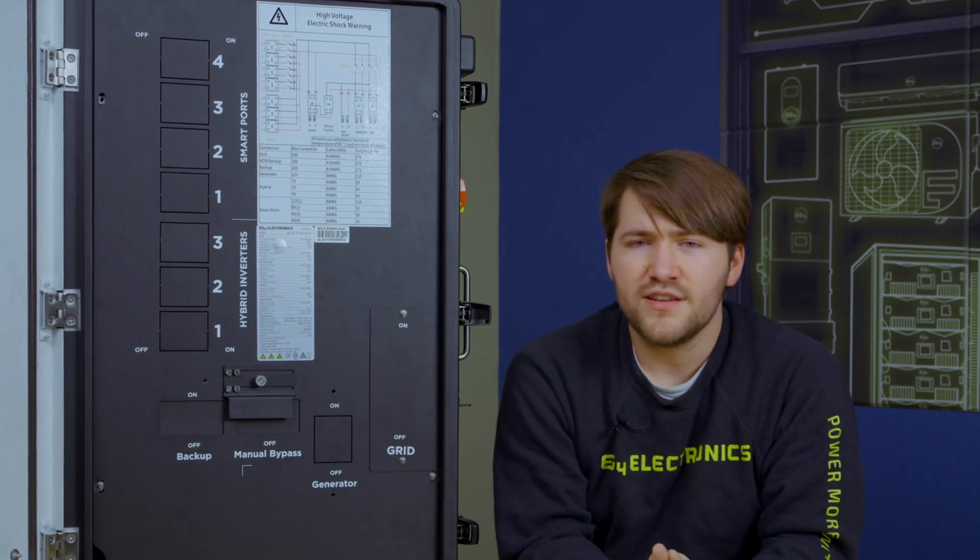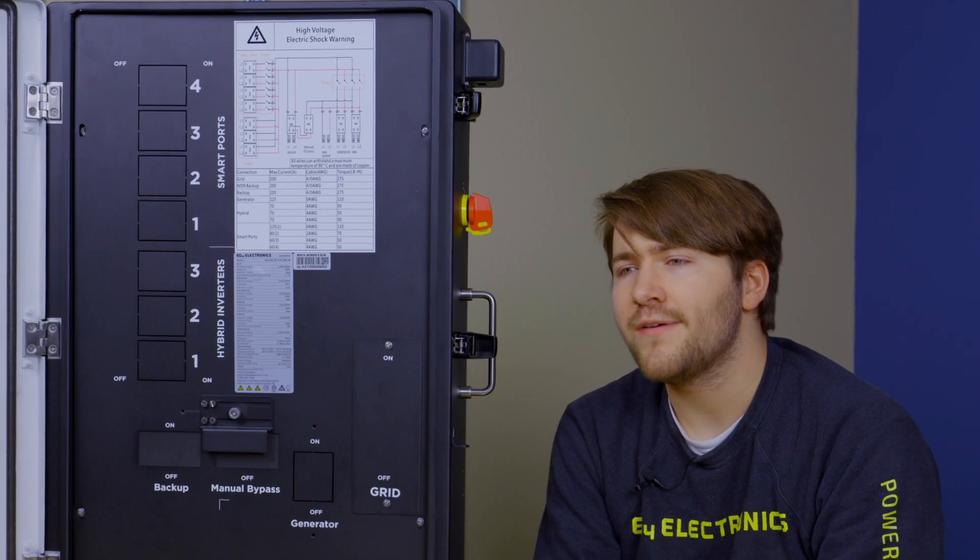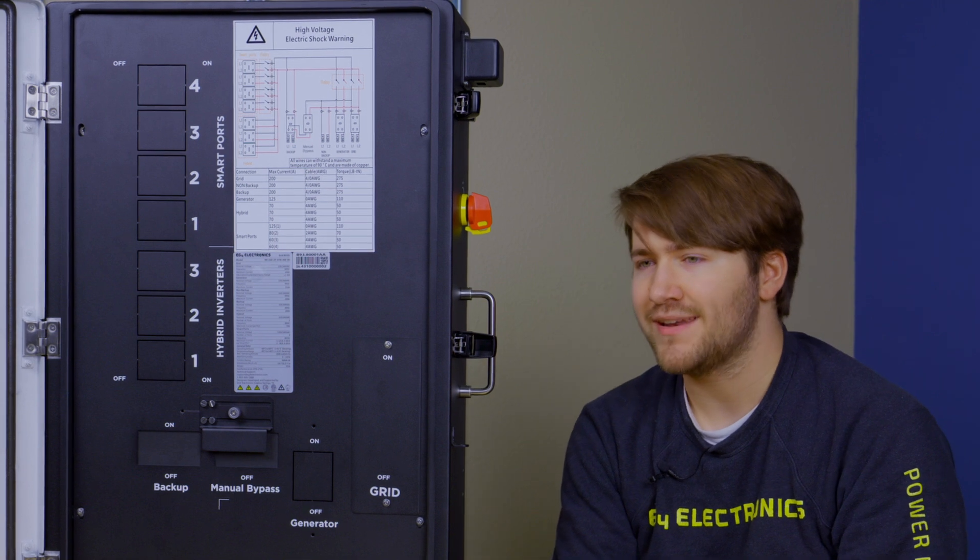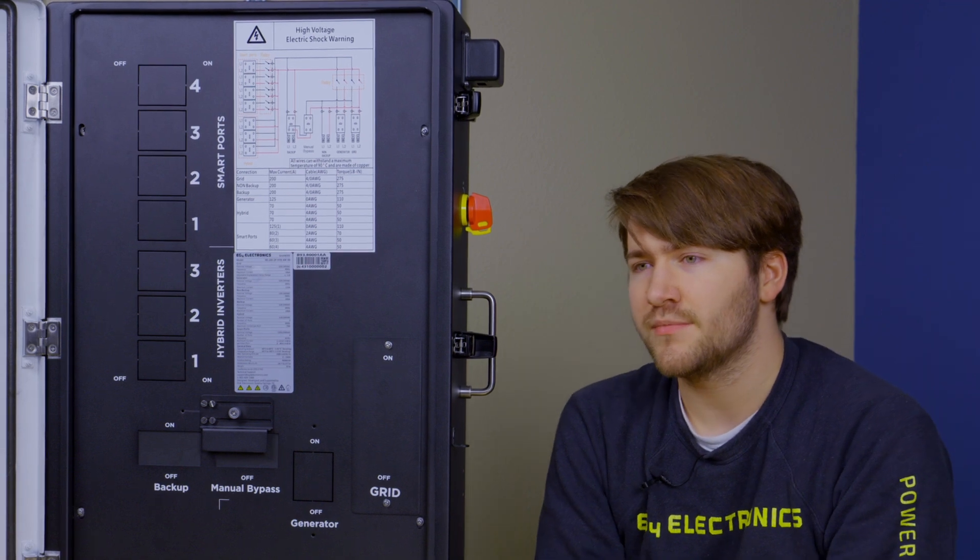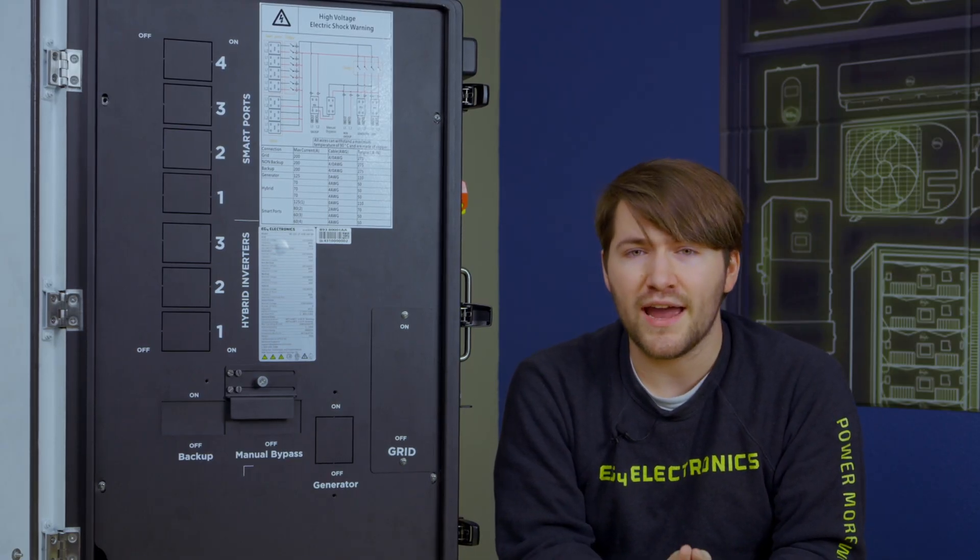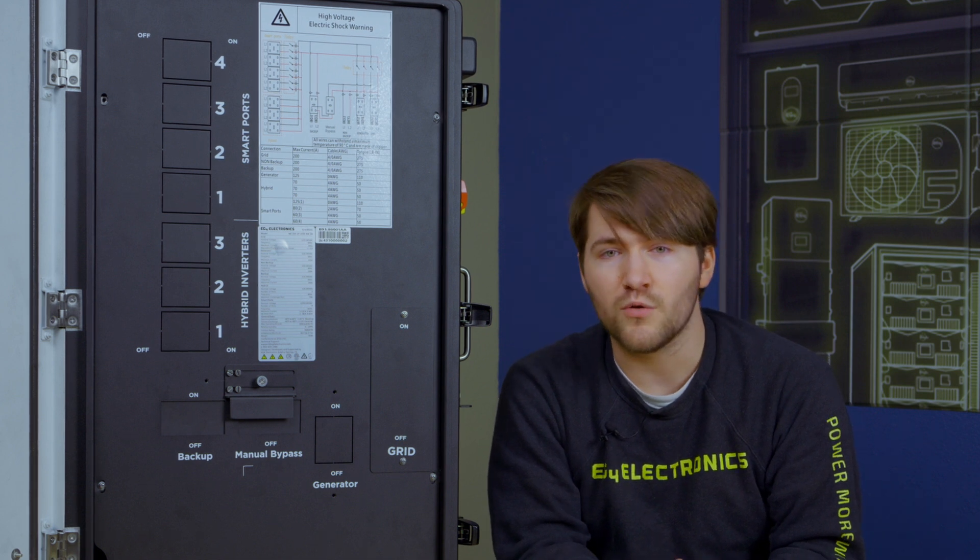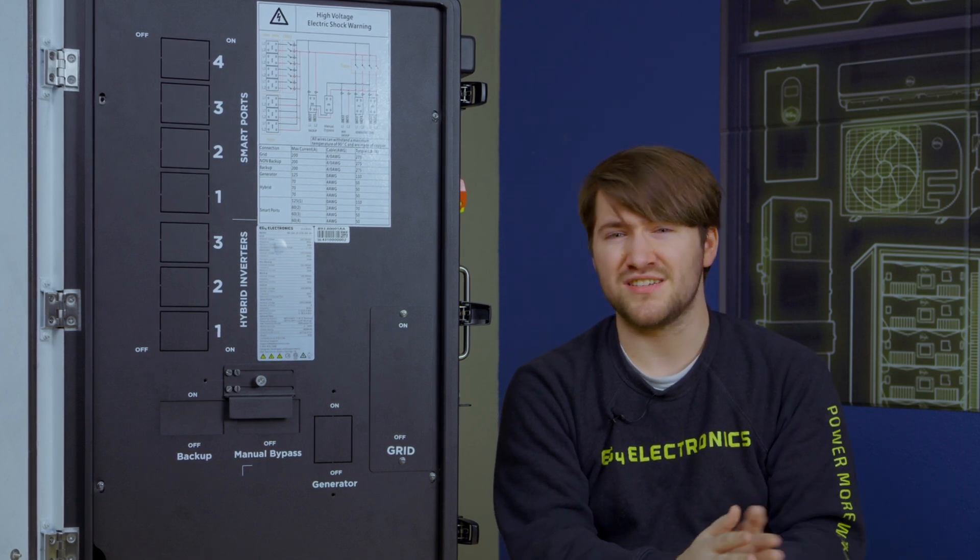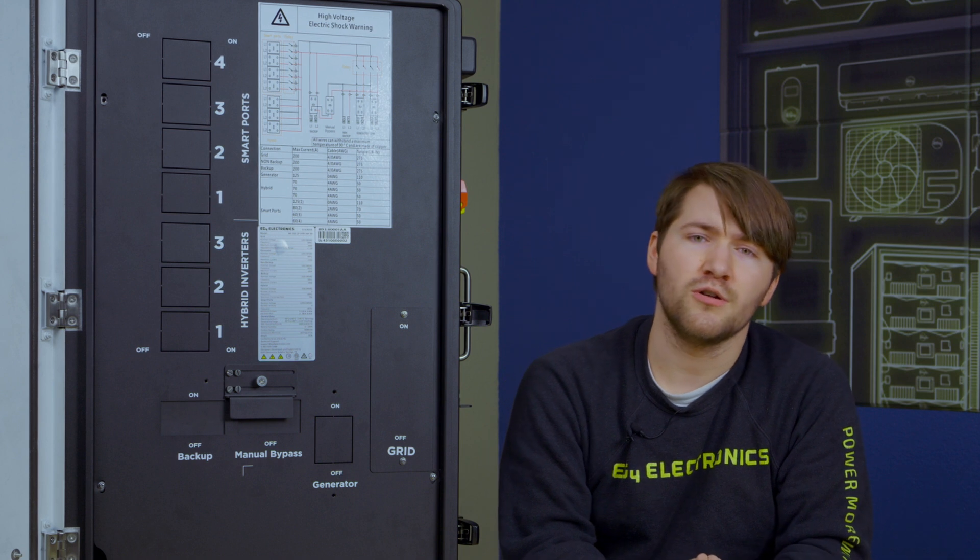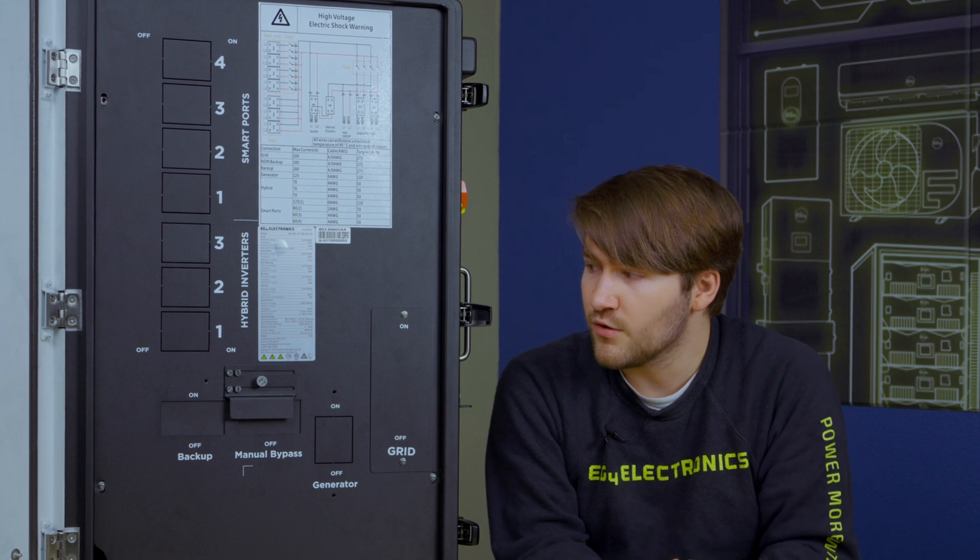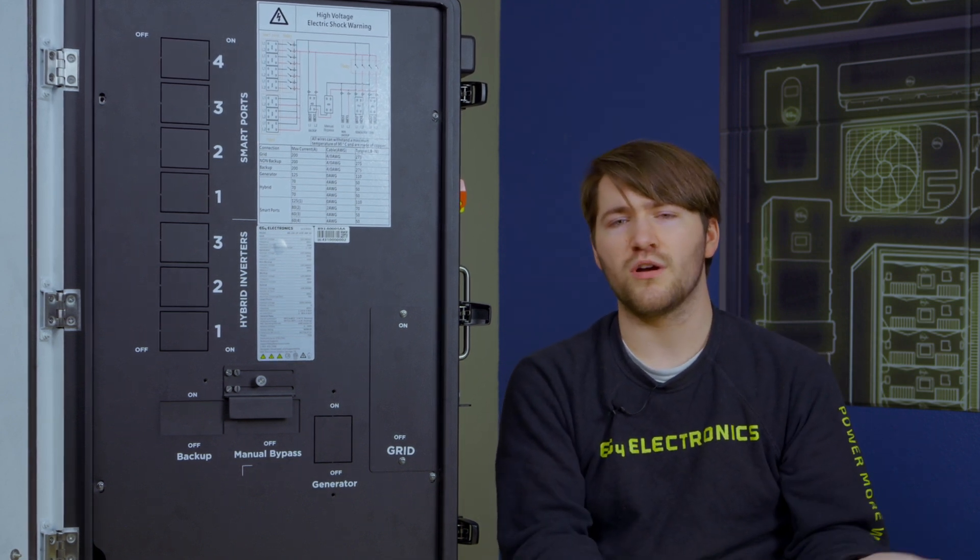And within these four smart ports, they each have different ratings. We have one at 125 amp, one at 80 amp, and two that are at 60 amp. Now, you can always put a smaller breaker in there if you have a smaller load or system that you are implementing into the port, but they do have some pretty high amperage ratings for all varieties of loads that you may be inputting. 80 amp is going to be a pretty common one for AC coupling. If you have a critical or auxiliary 100 amp load panel that you want to slot into a 125 amp breaker, you're able to do that. And then we have the 60 amps for other things such as an EV charger or AC.